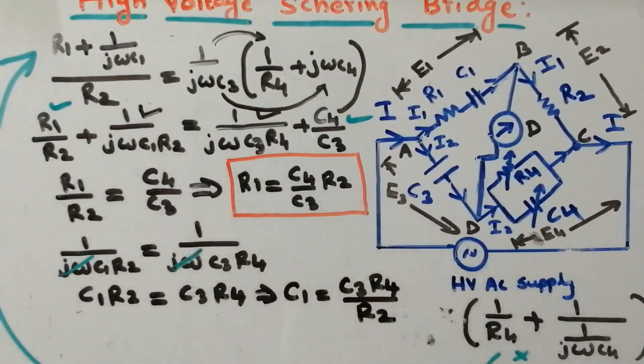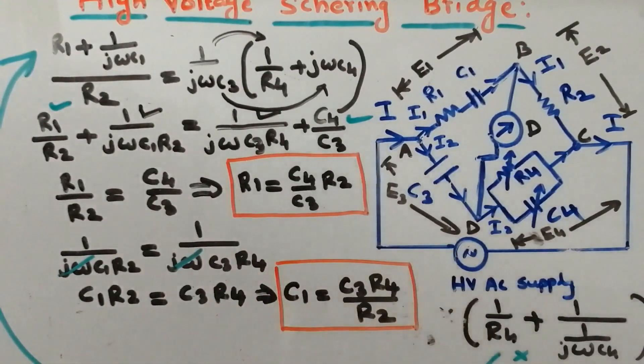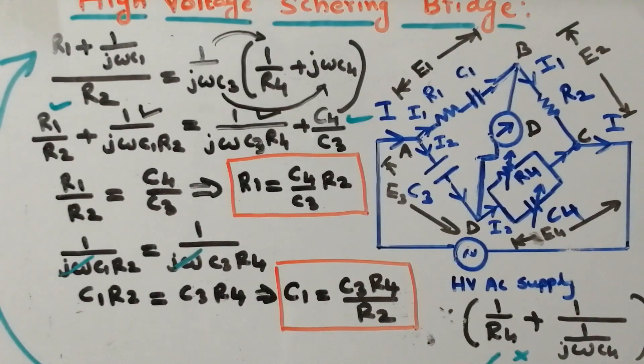Therefore, the unknown value of capacitor C1 is given by C3 times R4 divided by R2. So the unknown values of capacitor and resistor are given by these equations, which will be helpful for calculation of dielectric loss.